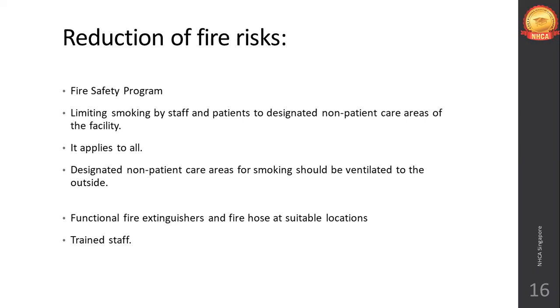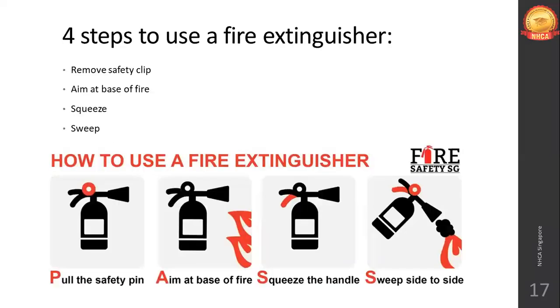Fire extinguishers must be checked to ensure they have not passed their expiry date and remain functional. Fire hoses should be available in all suitable locations, and staff should be trained to break the glass and use them. The four steps to use a fire extinguisher are: pull the safety pin, aim at the base of the fire, squeeze the handle, and sweep in a sweeping motion.